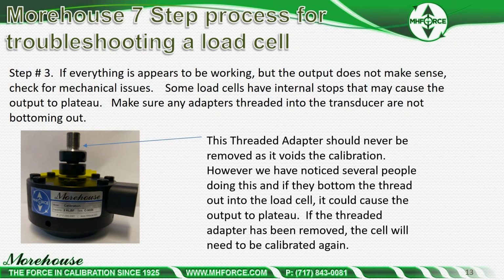If the thread adapter has been removed, the cell will need to be calibrated again. You will not repeat the thread depth. The thread depth in here is quite different, and the output is quite different depending on what the thread depth is. So if you've removed this, it needs to be recalibrated.